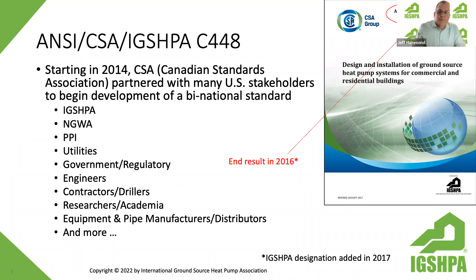So you'll see verbiage in there that says something to the effect of, this particular standard in Canada, or this standard in the US. So every clause indicates both countries, and it makes for a really easy to use standard and something that can be consistent. If you think about it, really an installation shouldn't be any different across North America. Obviously, the ground temperatures are different. There may be some local code requirements that are different, but the basic installation and design should be the same across North America. They're very, very similar from northern Canada to southern US.